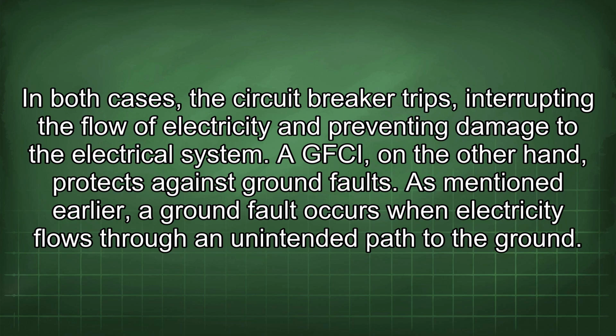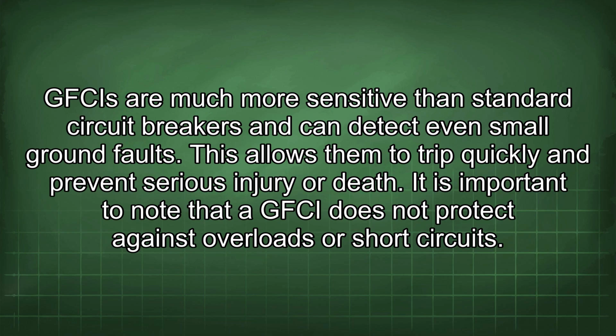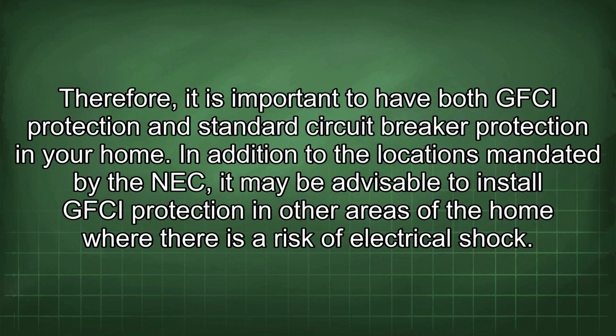A GFCI, on the other hand, protects against ground faults. As mentioned earlier, a ground fault occurs when electricity flows through an unintended path to the ground. GFCIs are much more sensitive than standard circuit breakers and can detect even small ground faults. This allows them to trip quickly and prevent serious injury or death. It is important to note that a GFCI does not protect against overloads or short circuits. Therefore, it is important to have both GFCI protection and standard circuit breaker protection in your home.